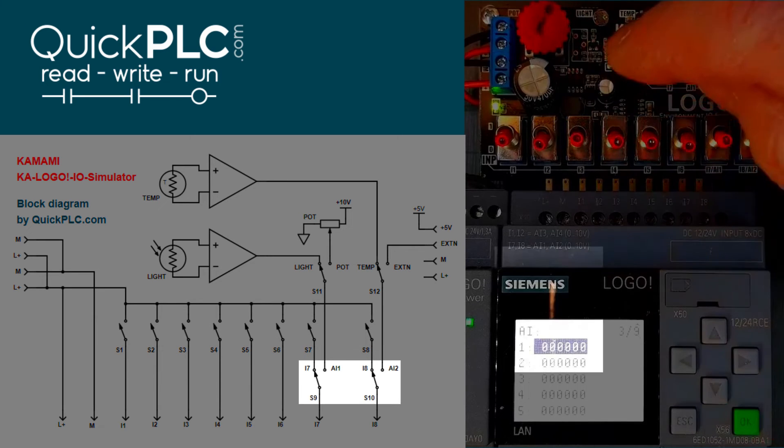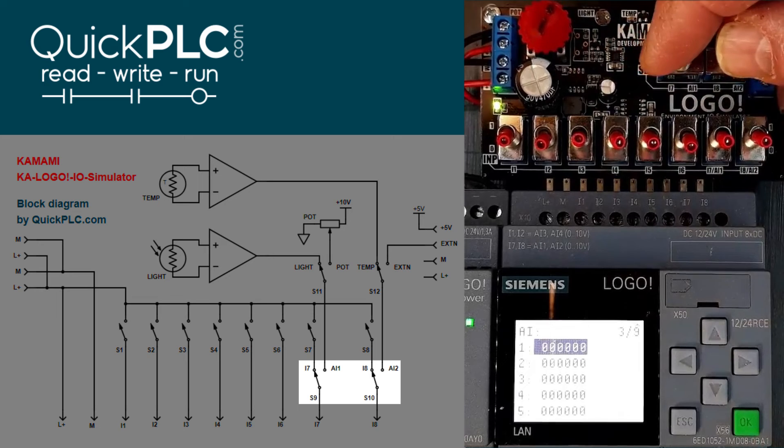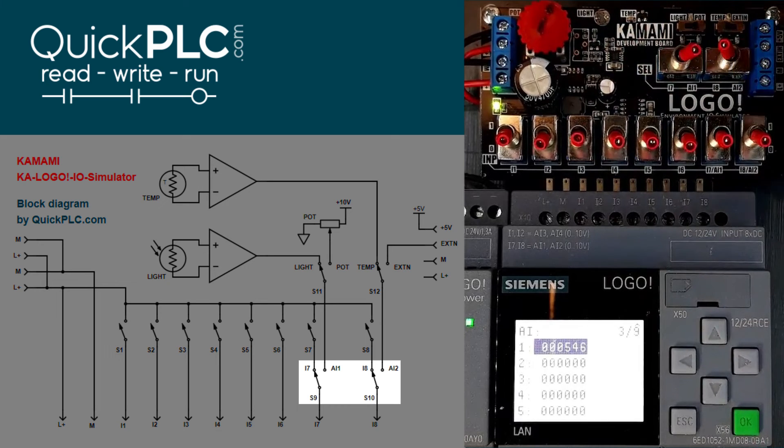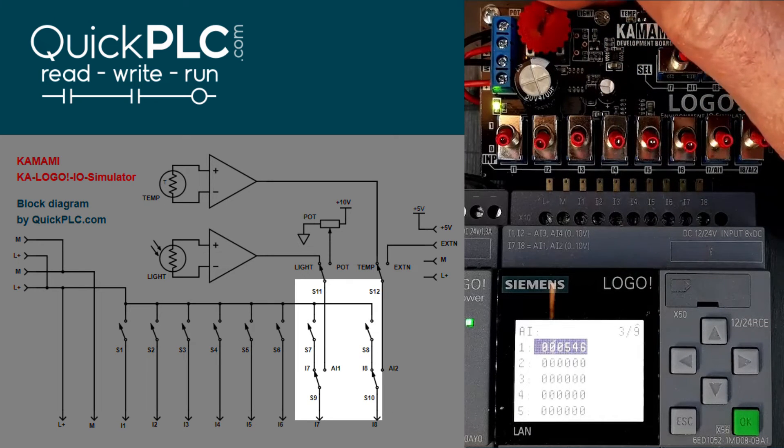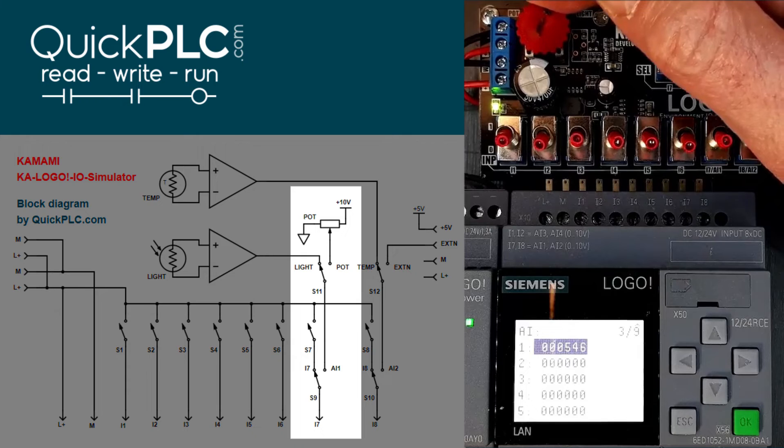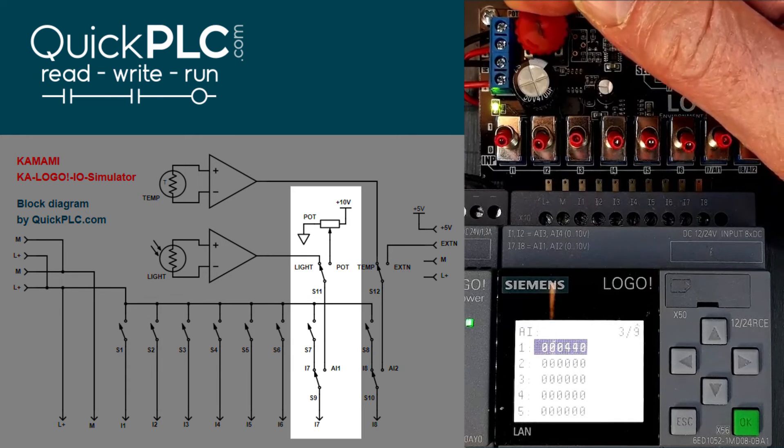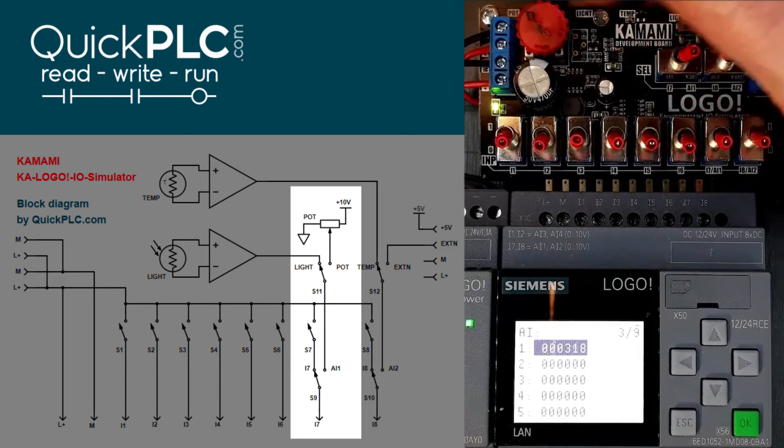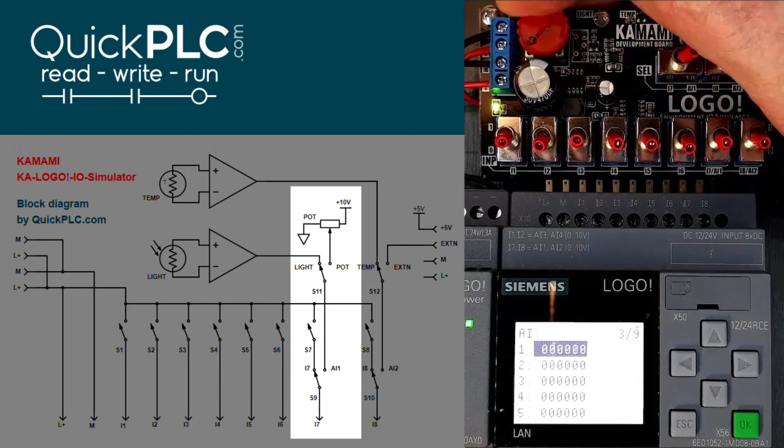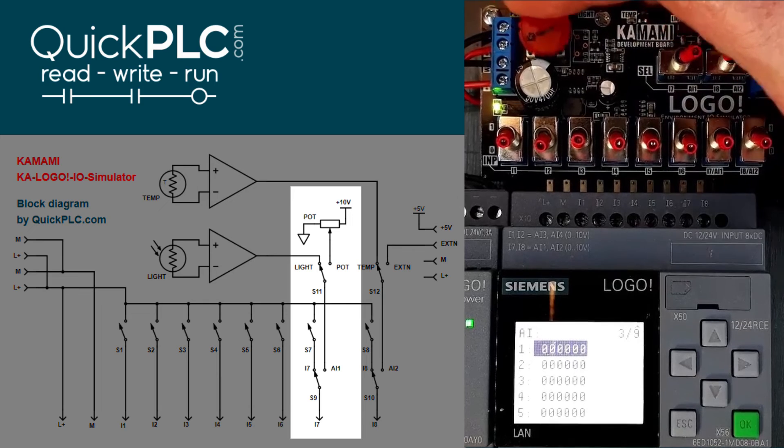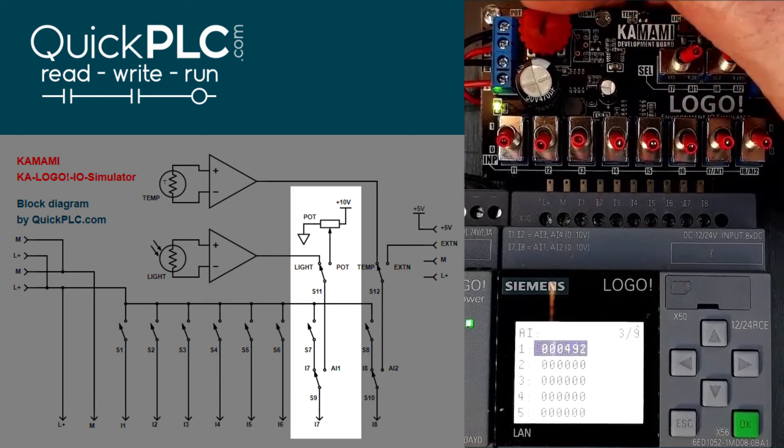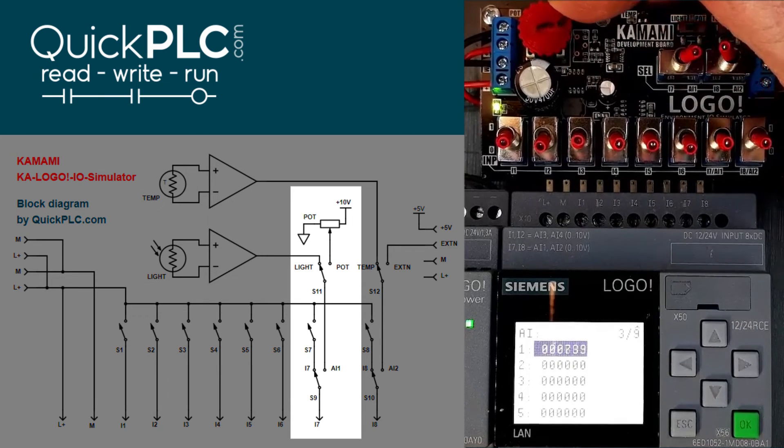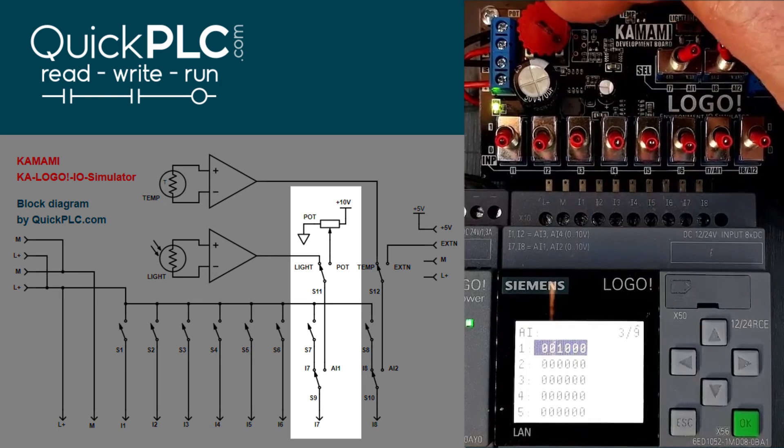Right again, we can test the analog inputs. So here we're selecting the potentiometer. And we can say input 1 is varying from fully anti-clockwise should give us 0 counts. And fully clockwise will give us 1000 counts for 10 volts.